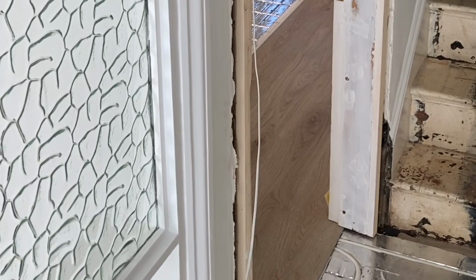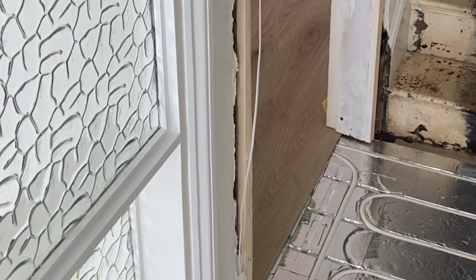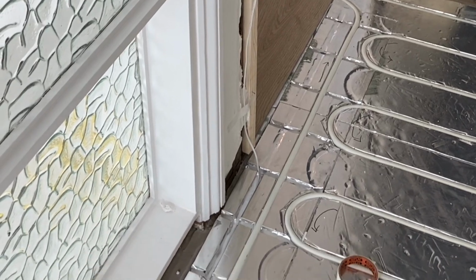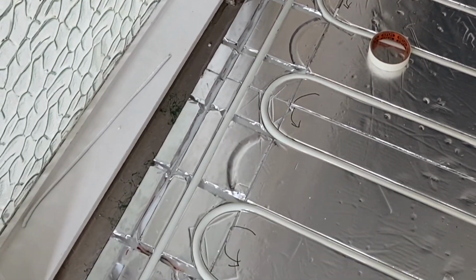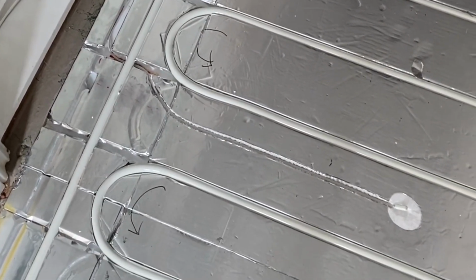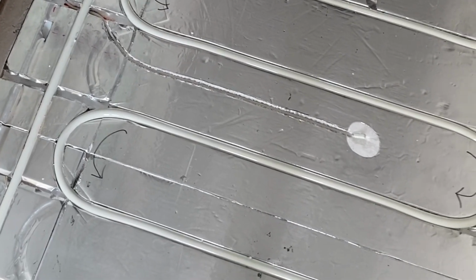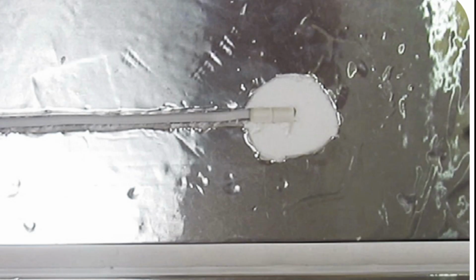Next, run the probe cable from the thermostat location down into the floor, ensuring the probe cable can be safely and discreetly routed. Make a channel in the board and position the probe between 2 heating pipes, but not touching them, and at least 30 centimeters into the heated zone. Cut the aluminium away surrounding the probe.